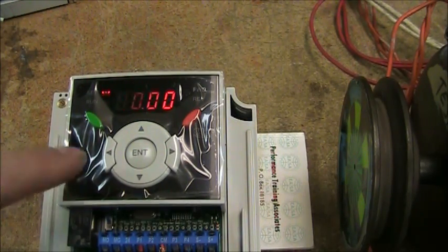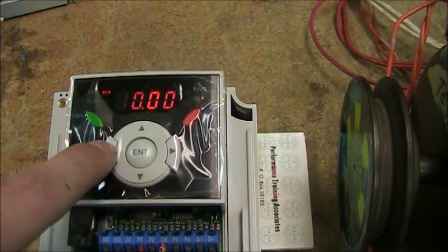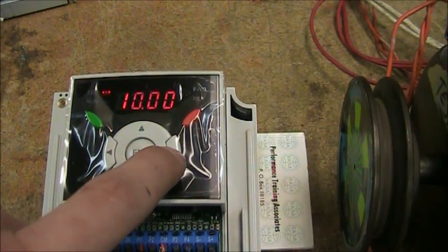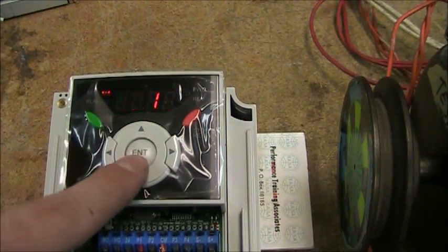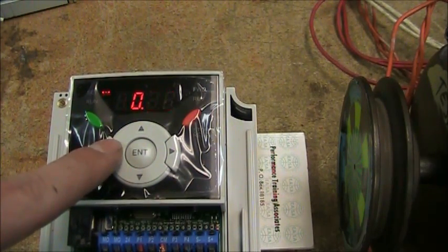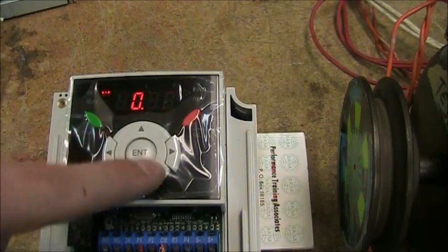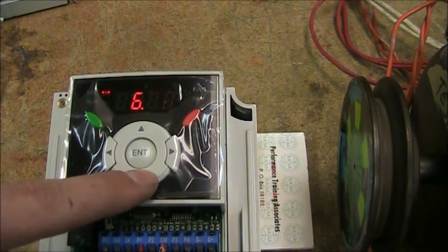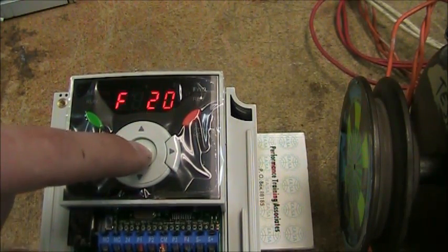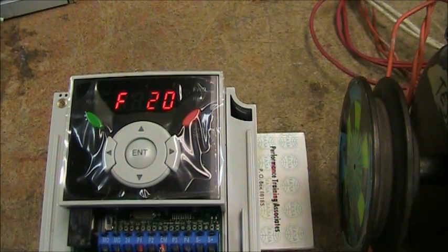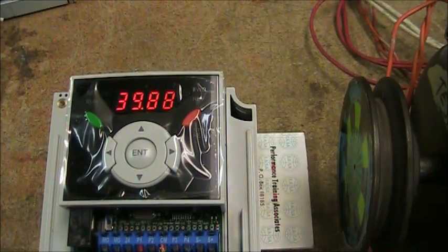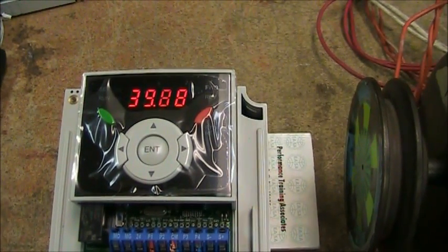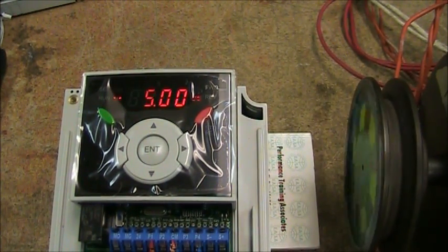Another thing that's interesting about this LED keypad is that you can use the side arrows to get to the correct decimal value. As you can see, right now I'd be setting in tenths if I go up and down. So to make it easier, I'm going to go over, and I have the 0 highlighted, and go down, and let's just make it 5 hertz. Again, you want to hit enter twice. Now that's set. I'm going to go back to my main screen, and when I flip my switch now, we should run at a jog frequency of 5 hertz that we set, which is the case.